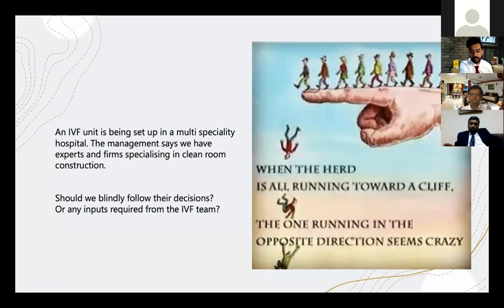You can look at primary filters, because the HEPA filter is your last line of defense. And before that, what is it protecting the HEPA filter? As Dr. Jacob mentioned, the molecular filter and the primary filter before it. So we can design some filters in the system which can take the bulk of the pollution and help cushion life for the HEPA. But despite all this, regular monitoring of air quality, you cannot run away from that. And these are cities where pollution levels are nowhere close to what we face in India. Yeah, so that's also something that we should note.